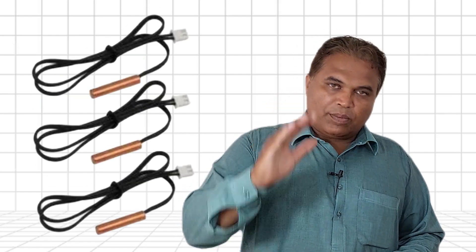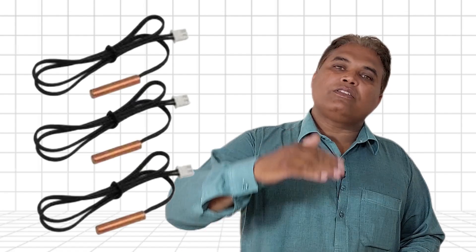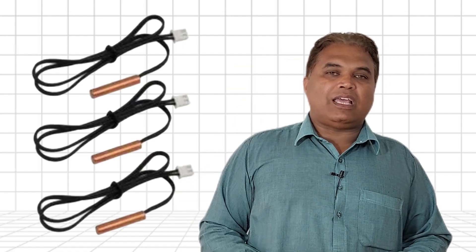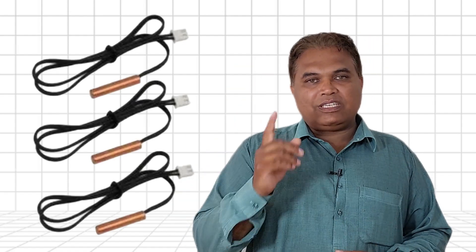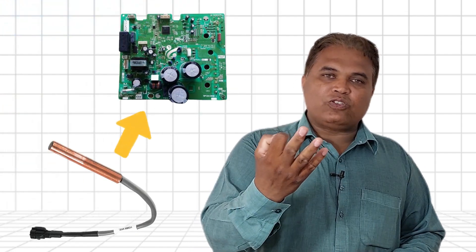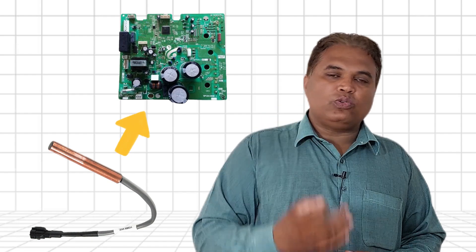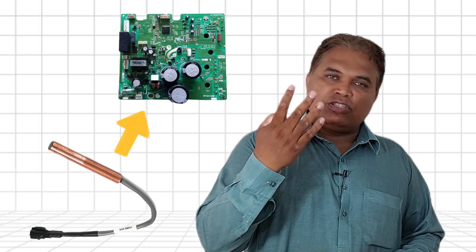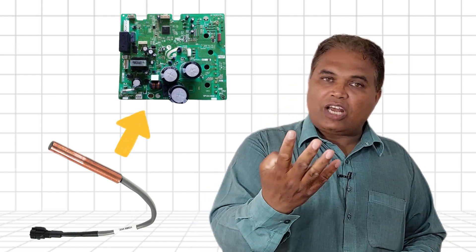However, in units with only three sensors, problems can arise because they typically lack a sensor on the suction pipe. In contrast, units with four or five sensors include a suction pipe sensor that monitors the temperature. If excessive cooling is detected, the sensor communicates with the PCB to reduce the compressor speed, preventing ice from forming. In summary, ice on the suction pipe in inverter or DC inverter units is rare, even if the refrigerant is overcharged. However, units with fewer sensors, particularly those without a suction pipe sensor, are more prone to such issues.